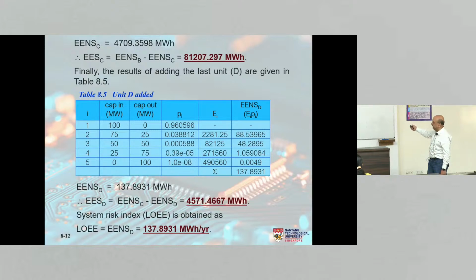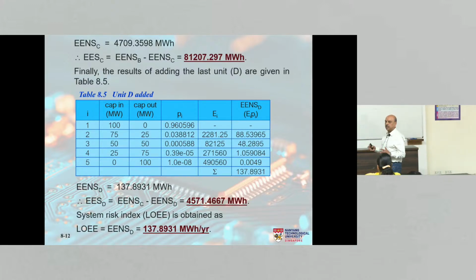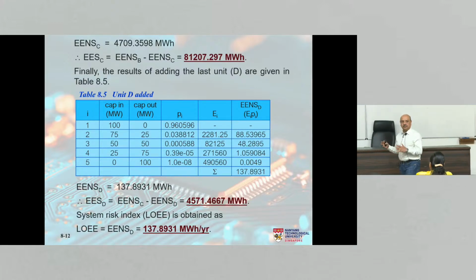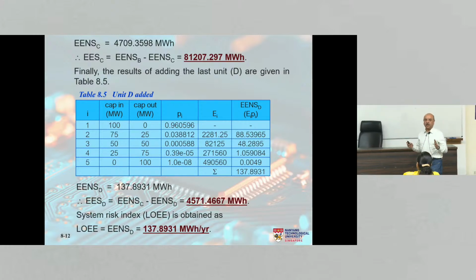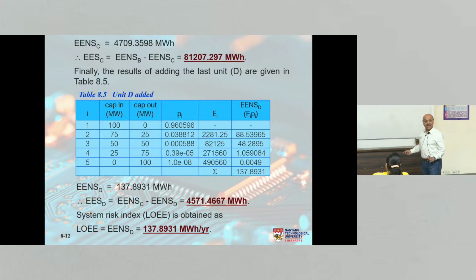So this is the risk in the system. I have now loaded all the generators in a priority loading order, and I find that the risk in the system is 137.89. Please note that if you load them in any other order, the risk will be the same. The risk cannot change.